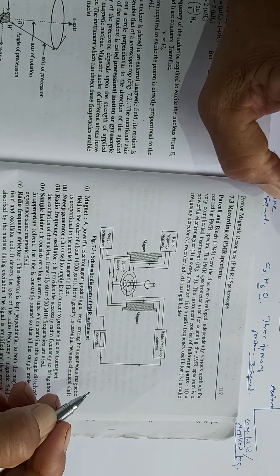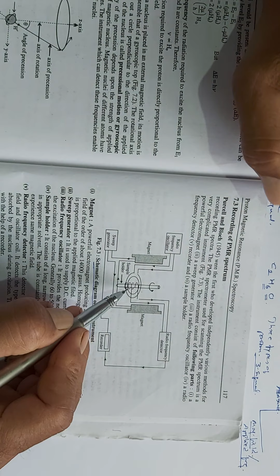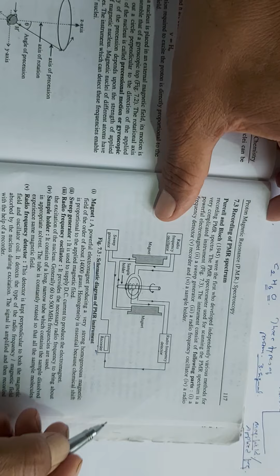When the sample is placed here, the magnetic field is applied and radio frequency is passed constantly, and this sweep generator varies the magnetic field from minimum to maximum, and the sample is exposed. When the magnetic field created by the nuclei and the magnetic field applied become equal, that is, the frequencies become equal, the sample undergoes excitation, and these excitations are detected by the radio frequency detector. When detected, they are recorded in the recorder. In this way, we get a spectrum of absorbance versus magnetic field, and we get different kinds of signals for different kinds of protons.